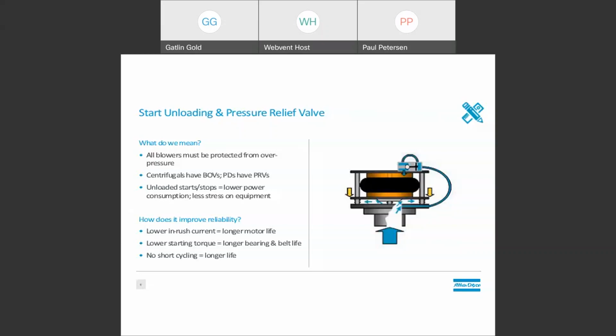Unloading at startup also reduces the inrush current to the motor. That reduces the electrical demand charges on some of the largest motors installed in the wastewater treatment plant. Right? Blowers are typically the single largest energy consumer. So if we can bring down that demand, that's a significant cost reduction. Unloading also results in lower starting torque on the drivetrain, extending the life of bearings in the blower and motor and belts or coupling elements.